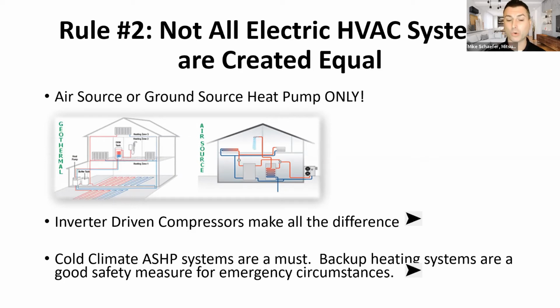We know it gets cold here in the winter, but ambient air temperatures don't usually get into the deep negative temperatures. While we're at 100% capacity at -5, we're still maintaining on average about 82% capacity all the way down to -13 as well, with operation beyond that. So cold climate air source heat pumps are an absolute must when we're talking about heating these all-electric homes.